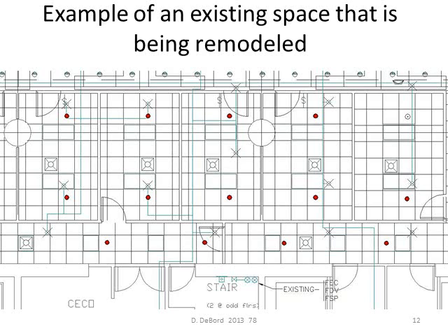And these could also have been upright sprinklers because they don't line up with the ceiling grid at all. Maybe the ceiling grid is all changed from the previous layout. I'm suspecting it was an existing developed building, just open with no ceilings, waiting for a tenant to come in. So it was what we call a base building, and then the tenant came in, and we're relocating.